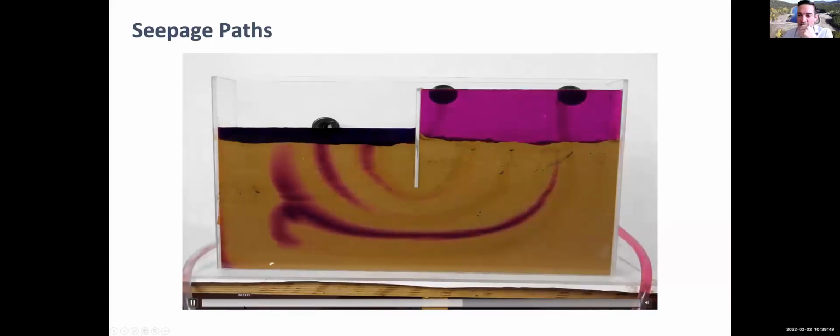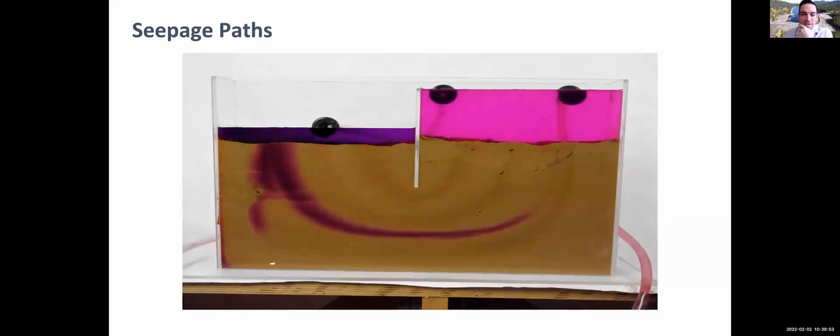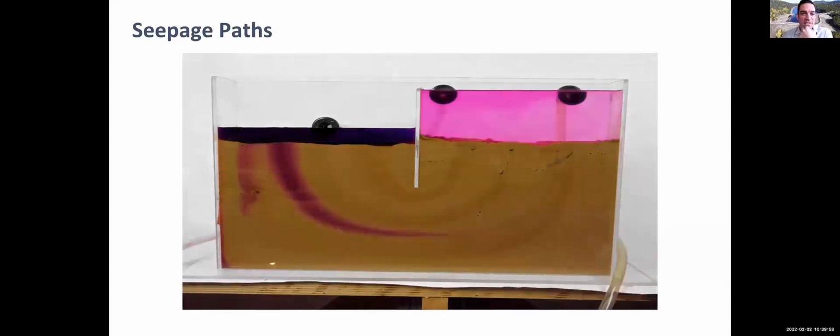We had a question: would stress cracks be what to look for if there are no piezometers? And we're going to talk a little bit about that. You definitely may see some internal erosion. If internal erosion is happening, you could have differential settlement. Differential settlement could cause cracking. Those types of things are indicators that there could be something going on. Could be excessive settlement in your foundation.